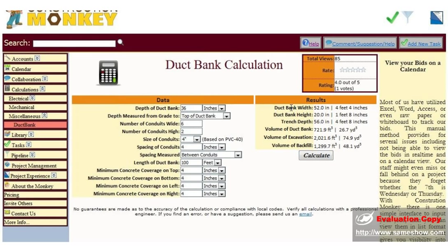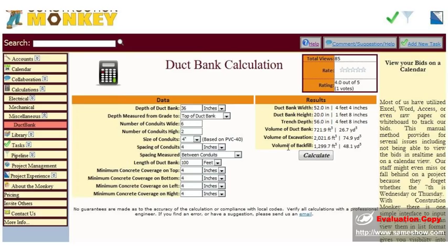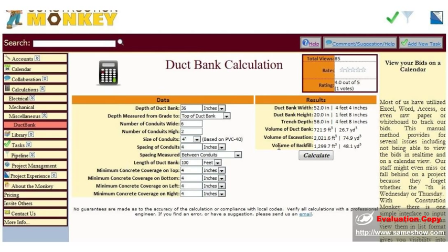And hit the calculate button. And it will give you your duct bank width, your duct bank height, the trench depth, the volume of the duct bank, the volume of the excavation, and the volume of the backfill you'll need.